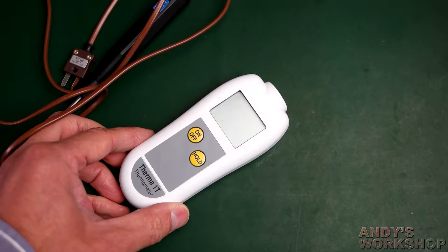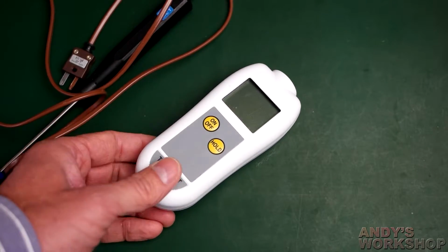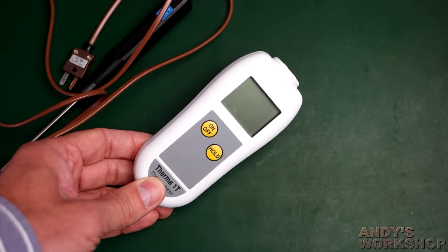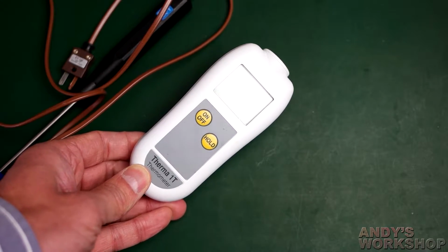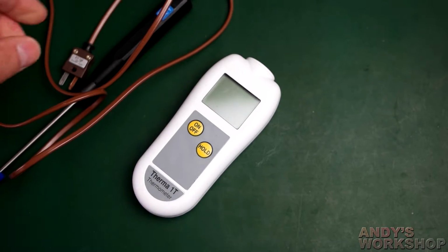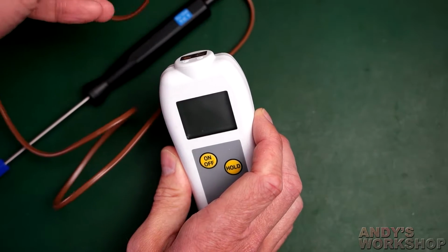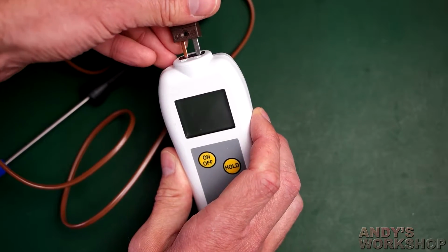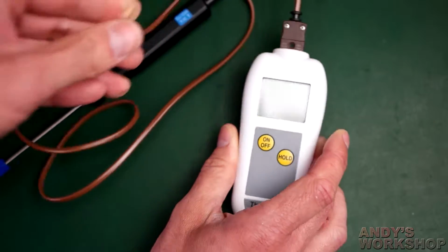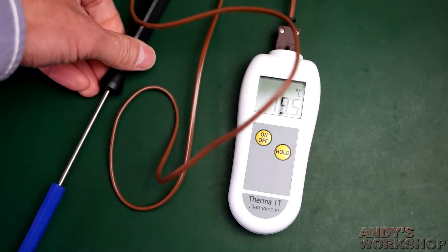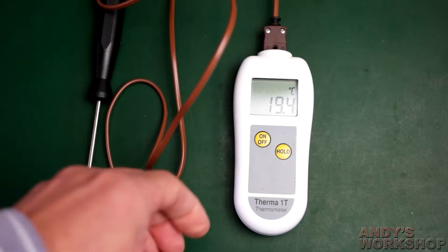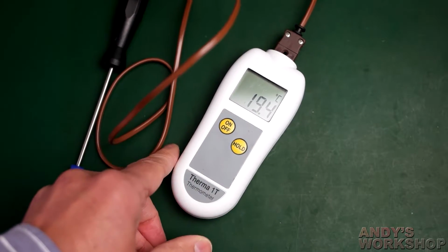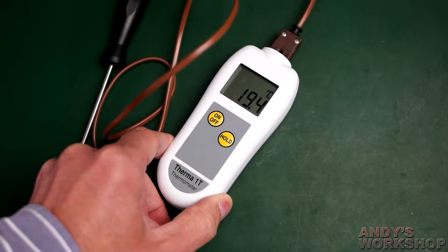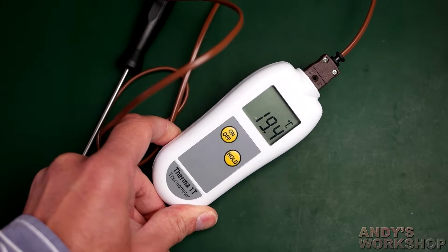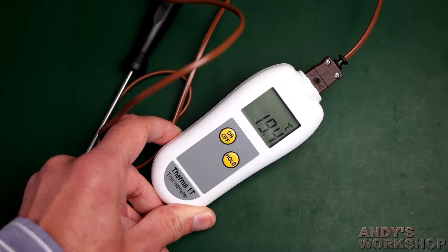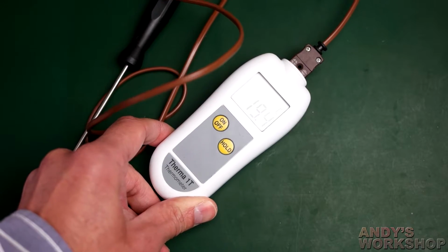So I did consider the thermocouple, and as an example, this is the one I use at the moment for my home brewing. It's a Therma 1T, which is a T-type thermocouple. It's more accurate than the K-type. This particular one comes with detachable probes that you can just plug in at the top here. If I put this in and switch it on, it comes on, and immediately it measures, it reacts quickly to change. This particular one was calibrated by the manufacturer when I bought it less than a year ago, so I consider it to be accurate, and I use it as a reference to see how well the other probes that I've got are performing.